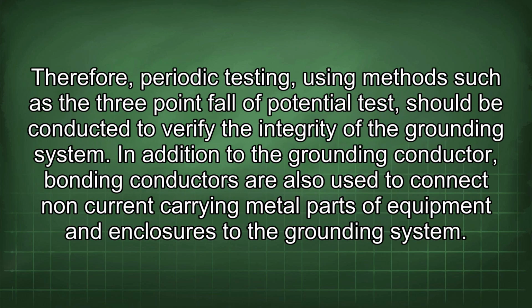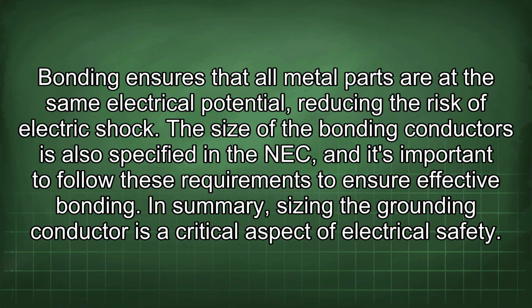Therefore, periodic testing, using methods such as the 3-point fall-of-potential test, should be conducted to verify the integrity of the grounding system. In addition to the grounding conductor, bonding conductors are also used to connect non-current carrying metal parts of equipment and enclosures to the grounding system. Bonding ensures that all metal parts are at the same electrical potential, reducing the risk of electric shock. The size of the bonding conductors is also specified in the NEC, and it's important to follow these requirements to ensure effective bonding.